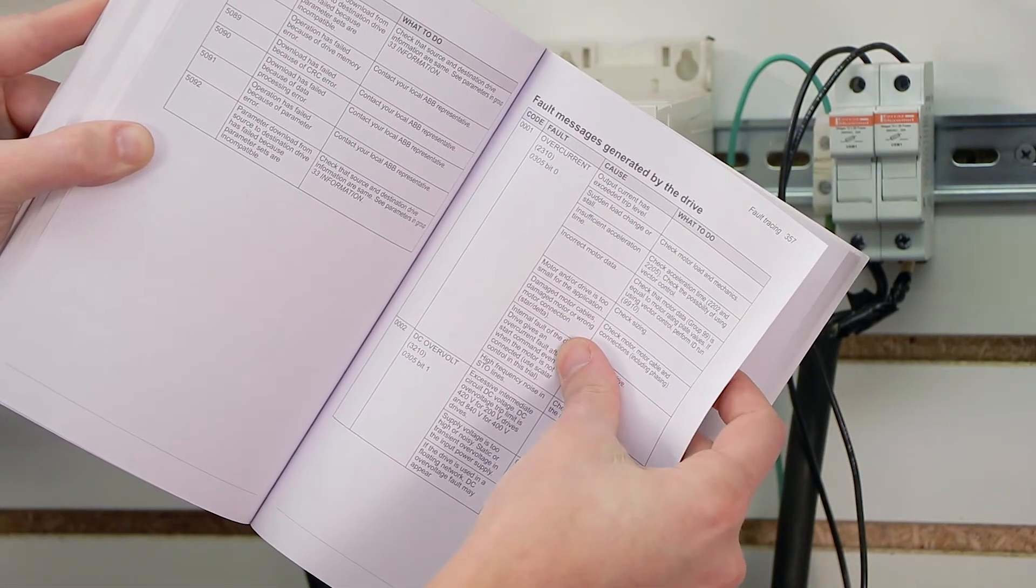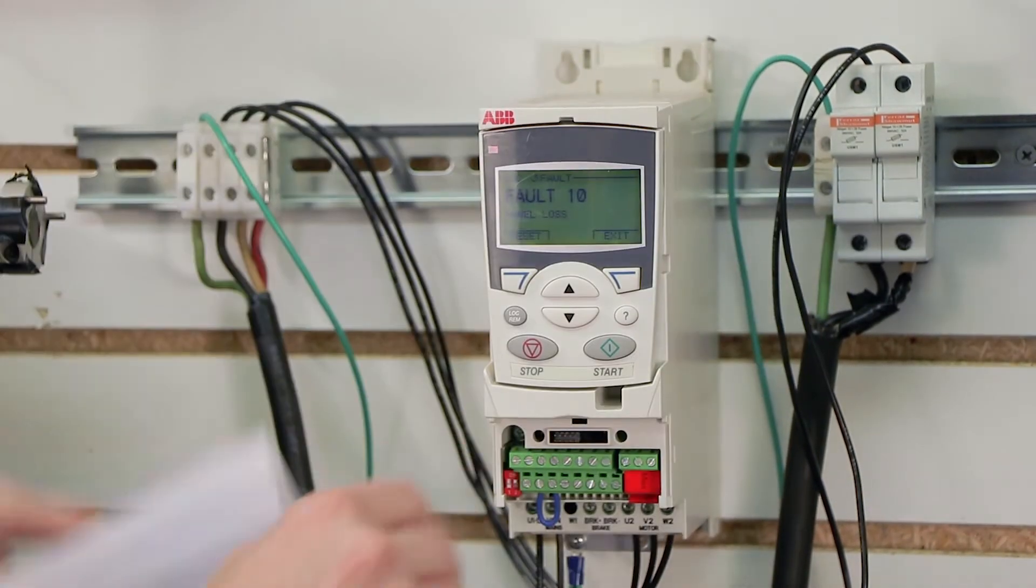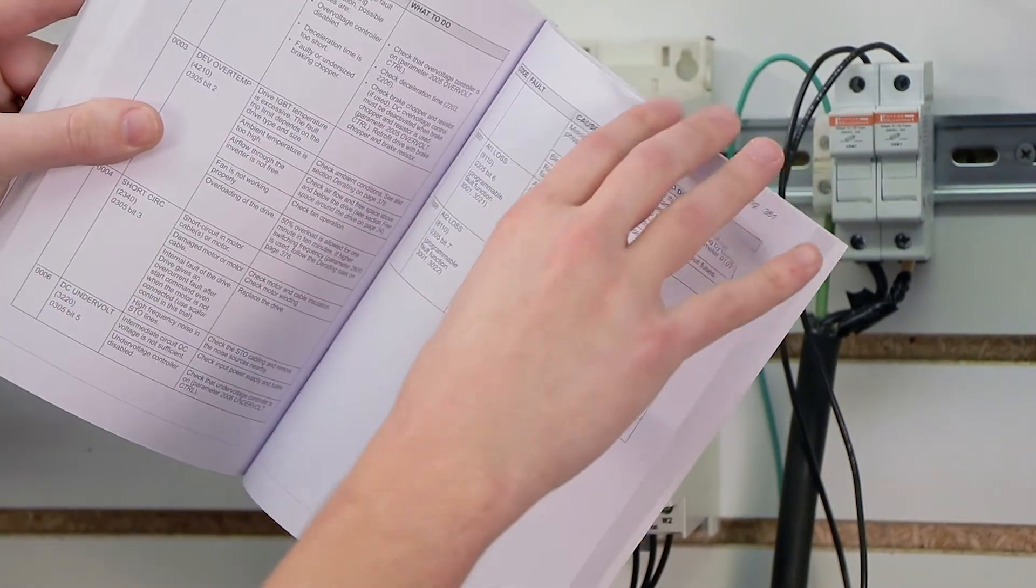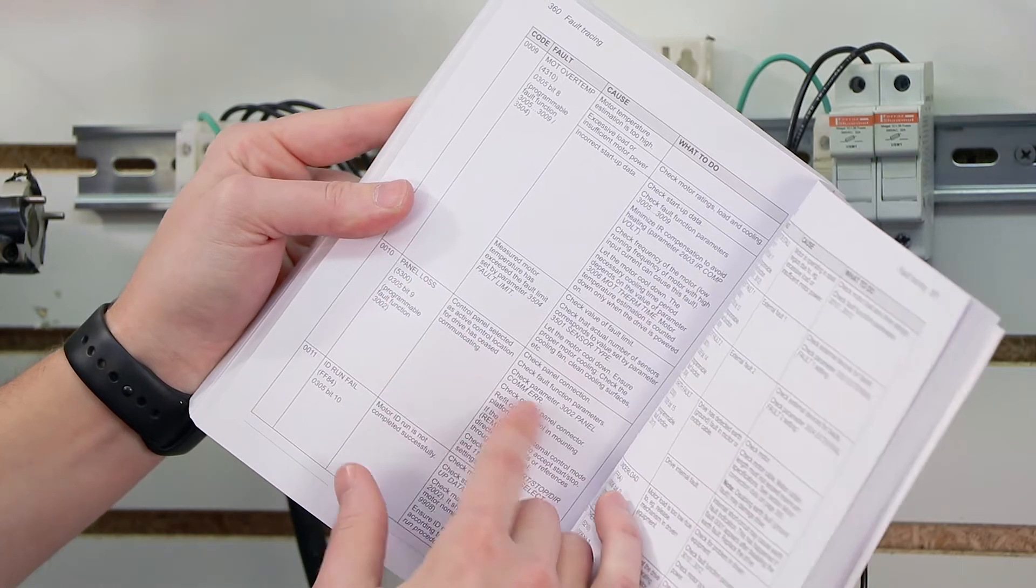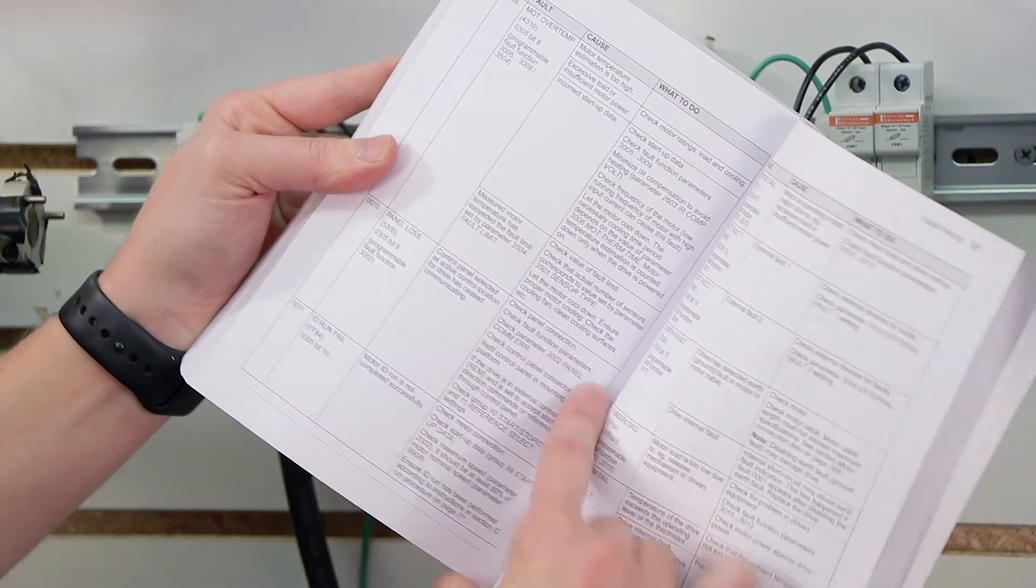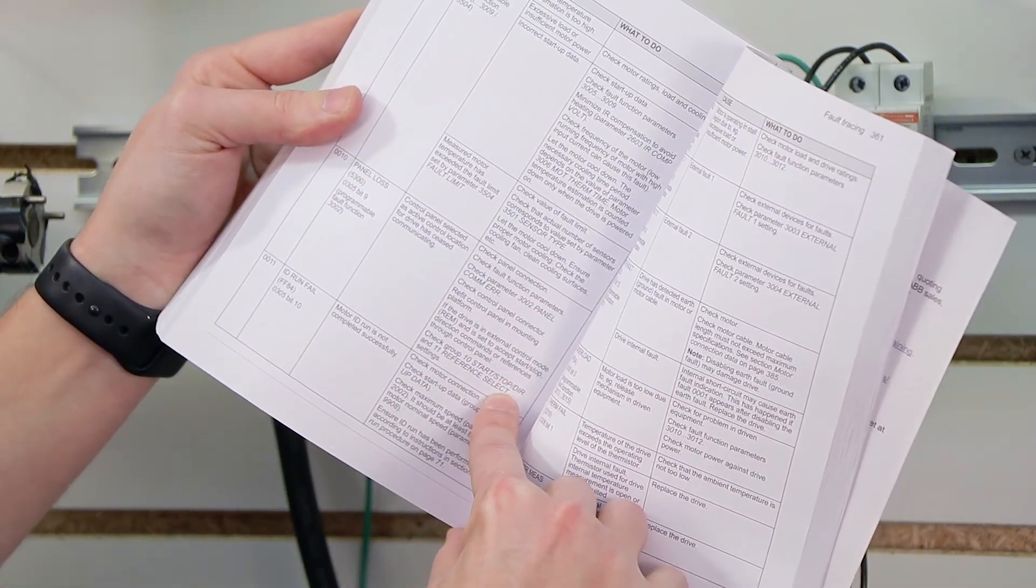We're going to go to the actual codes, which we had discussed. So this is code one, code two. We actually are on code 10. So I'm going to flip a couple pages all the way to code 10, panel loss. Once again, control panel selected as active control location has ceased communicating. Now it's giving me a ton of options of what I can do to possibly resolve this issue.